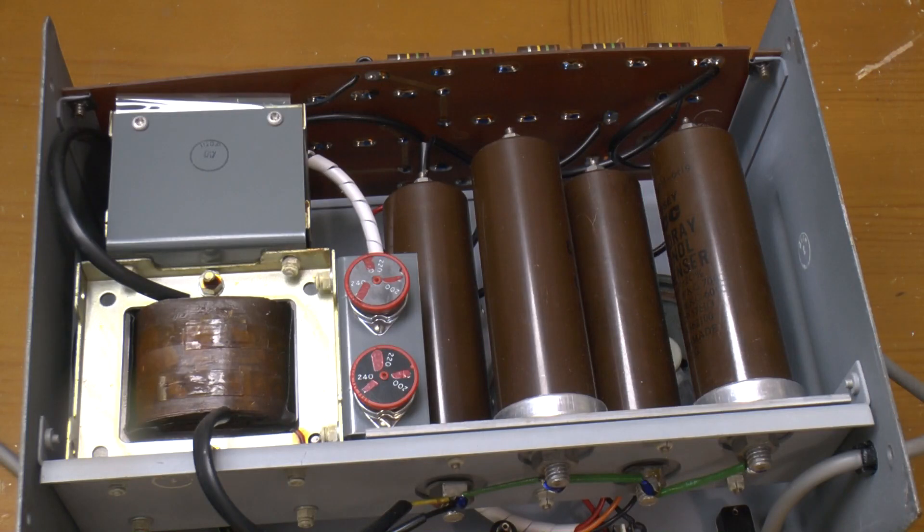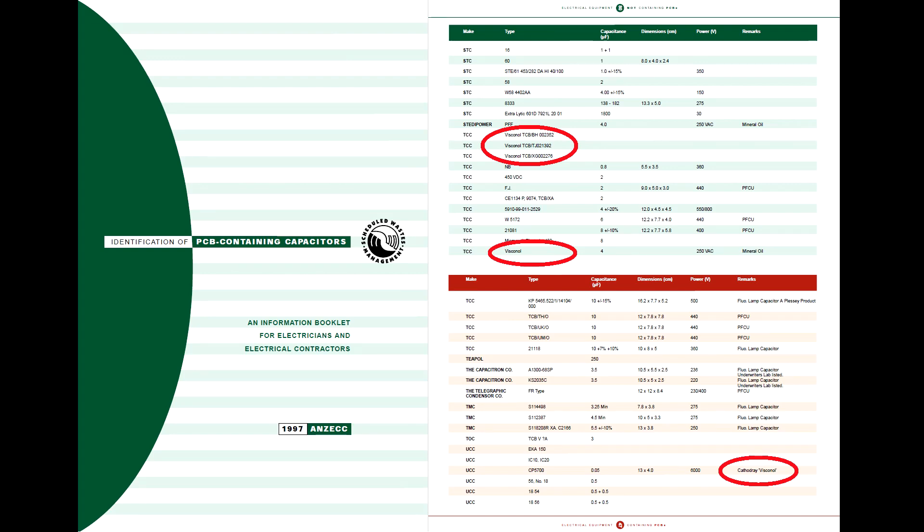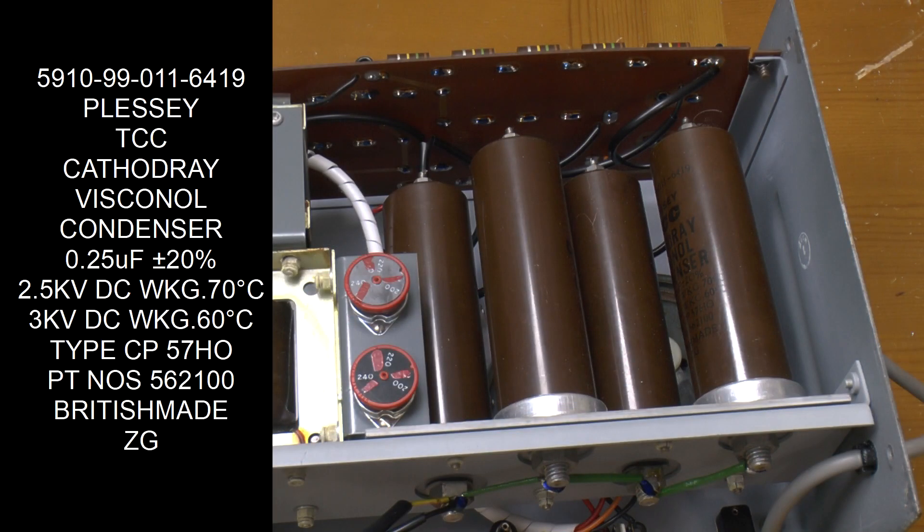Now as it's an oil and paper capacitor, obviously there's old oil inside but is it PCB oil? Well it's kind of hard to tell. There's a lot of conflicting evidence out there. The United Nations Environment Programme don't list Visconol as a PCB mixture. ANZECC have produced a list of various capacitors and have four Visconol caps in their green list of PCB free capacitors. However they do have the CP5700 in their red list of PCB containing capacitors. The caps in this unit are CP57HO which is the same family. At least they're not leaking and I don't intend chopping them open. As long as they don't go bang they should be fine I think.